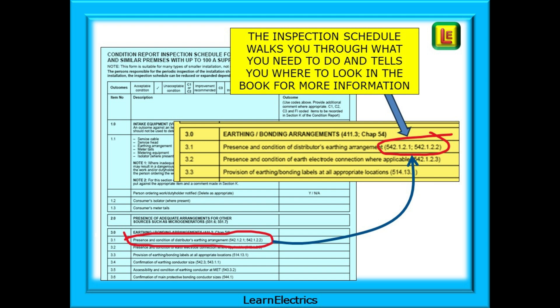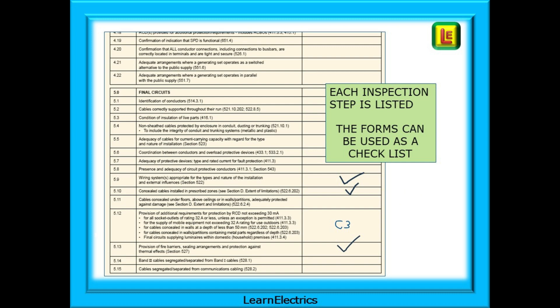The Condition Report Inspection Schedule pages will actually walk you through a periodic inspection. Each box on the schedule tells you what you should be inspecting and gives you the regulation numbers that apply. You can find further information and clarification in the wiring regulations book. Each inspection step is listed, and I would strongly suggest that you use the inspection schedule as a checklist so that nothing is missed. Many inspectors will use a rough copy to mark up on site and then transfer the data to a clean copy or an online form back at the office. All the information, all the prompting and help that you need is there — use it.